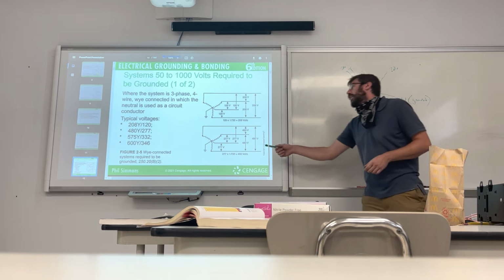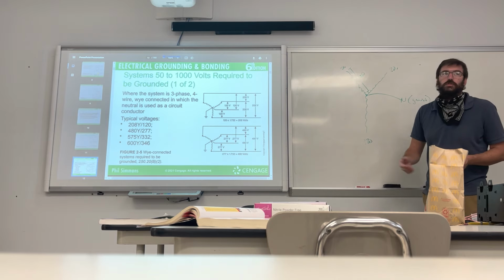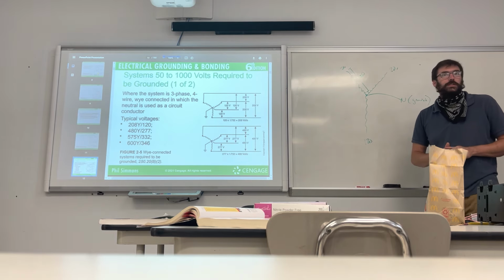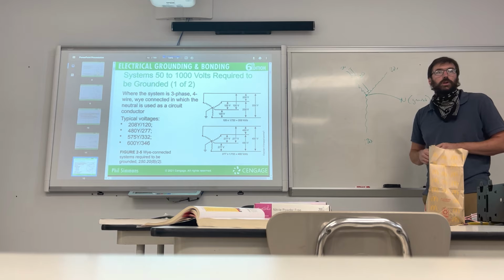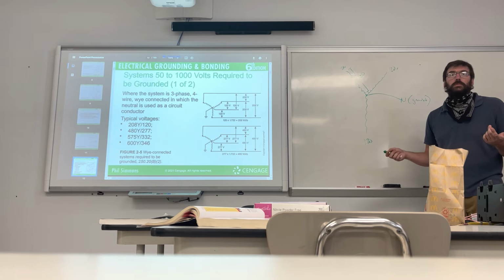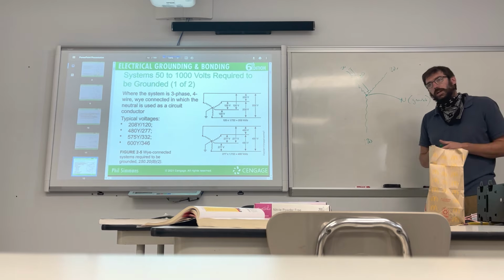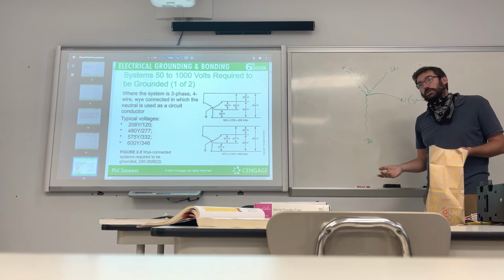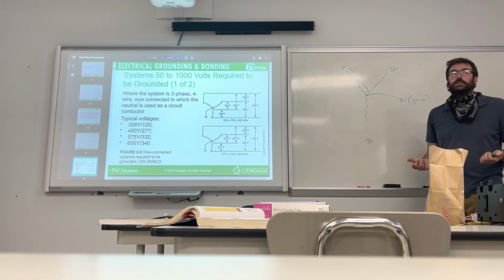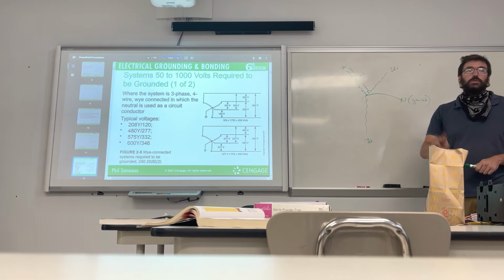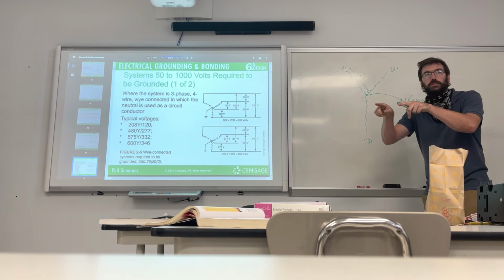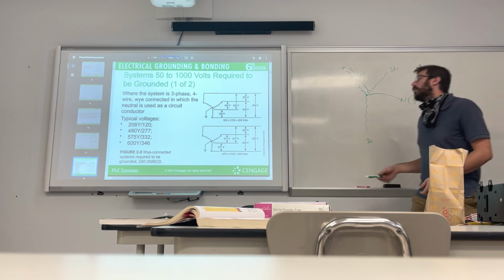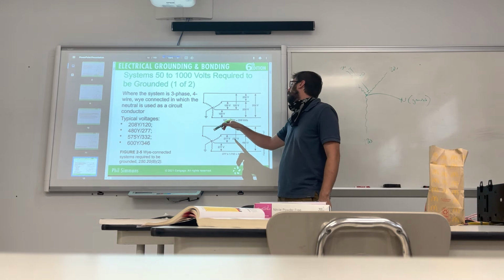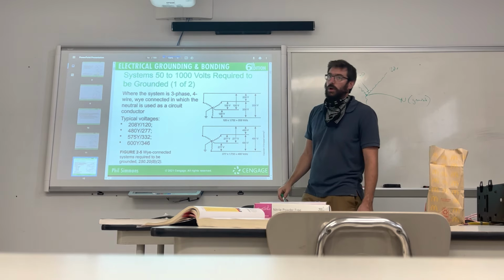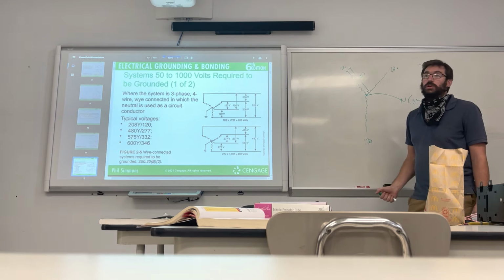I hope to have a better way of explaining that to you in the future, but just know that when you're dealing with a 3-phase panel or a 3-phase transformer, that 120 plus 120 does not always give you 240. Just like a 480 system, right? You cut that in half, what's half of 480? You would think each leg is going to be 240, right? But each leg is actually 277. 2 legs of 277, when you put your meter on it, it gives you 480. But once again, if you times 277 by 1.732, it will give you 480. So that's just how we get those numbers.